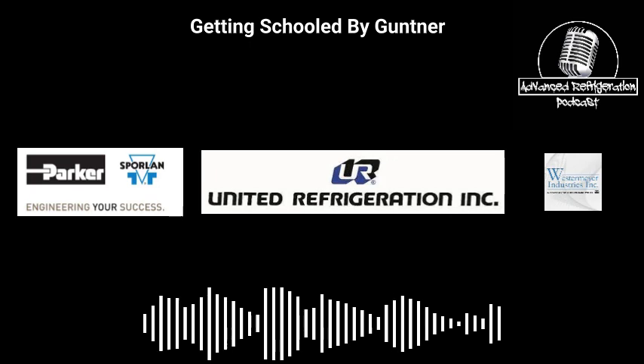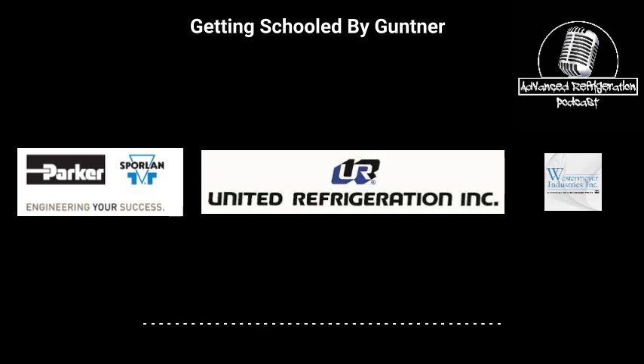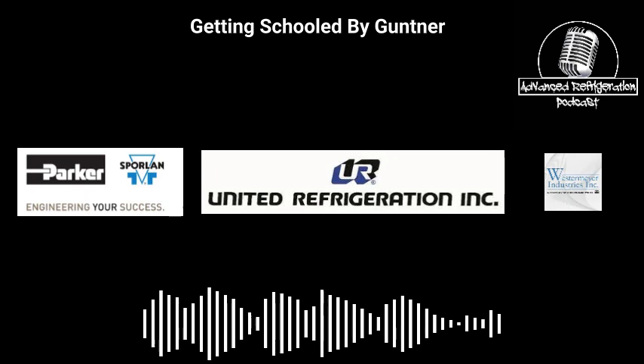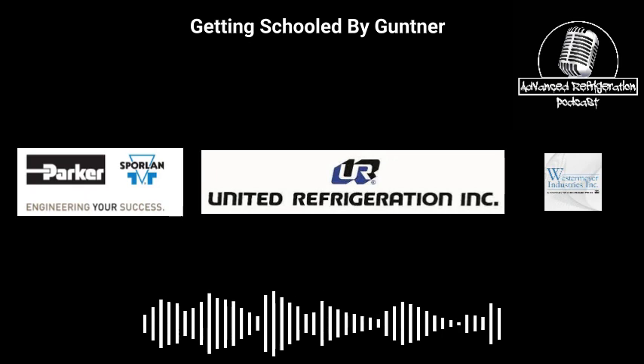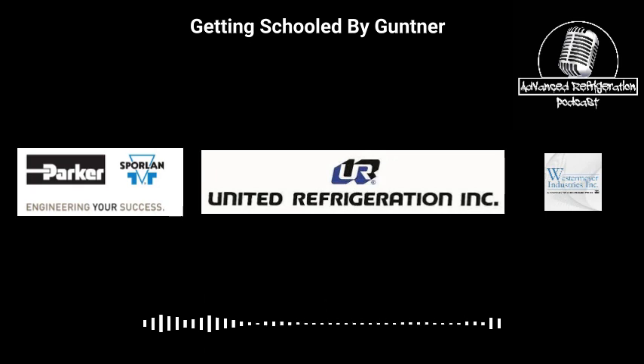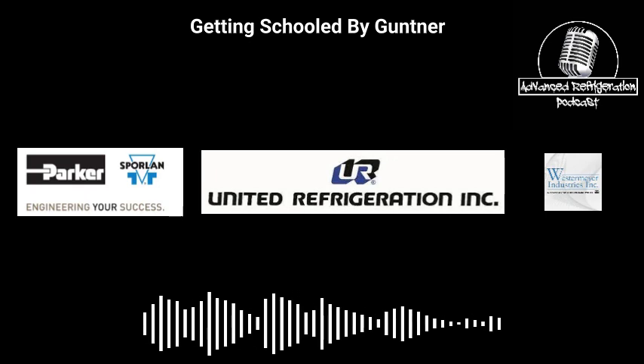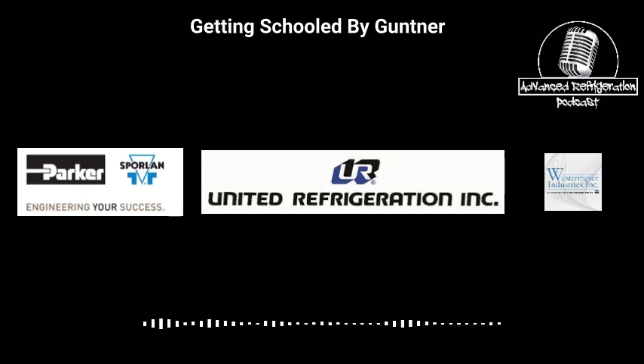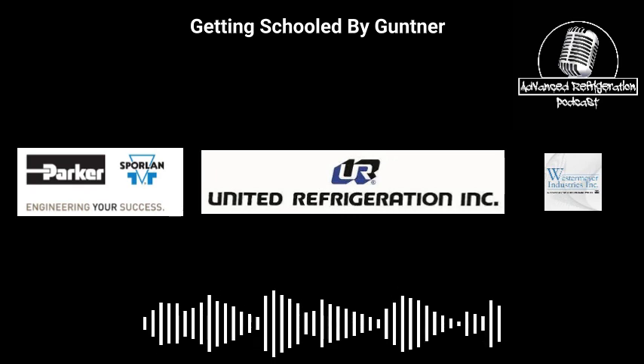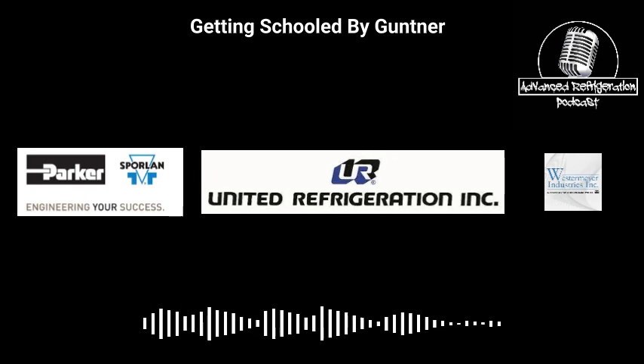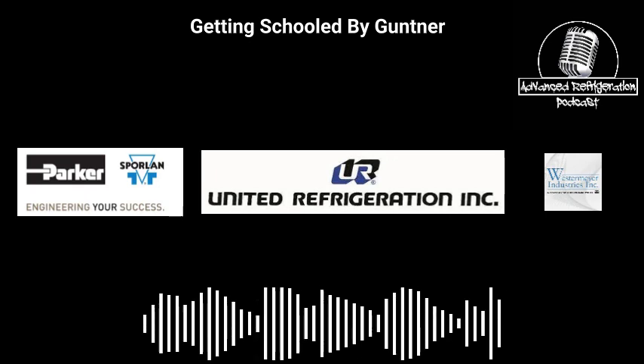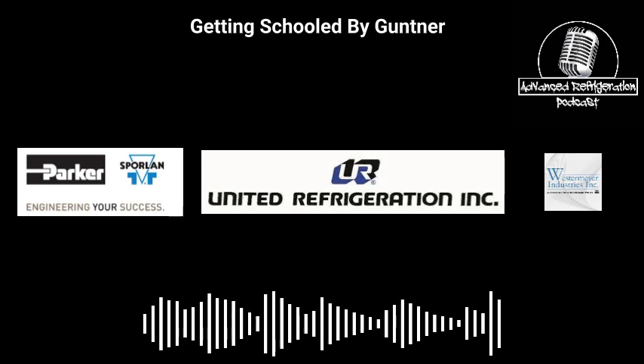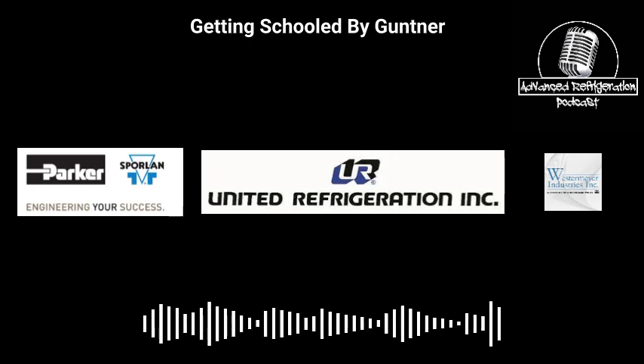And then another standard feature that we have is our ice break feature. What the ice break feature is, if, and I actually had a customer call me up in, I think, Quebec. They had a really nasty winter last year. And he was telling me that the fans were oscillating back and forth and then they broke free and he didn't know what it was. And it was because the ice was on there. Ice had formed on the fan and the fan started spinning back and forth and then breaks free and then starts spinning. If for whatever reason it can't break free, you'll get an operational message right on the controller telling you that it's not working.